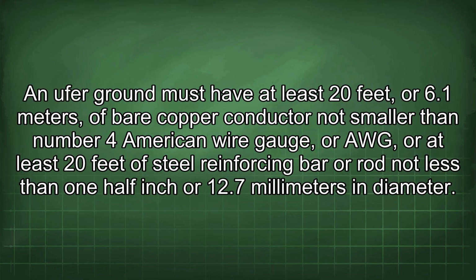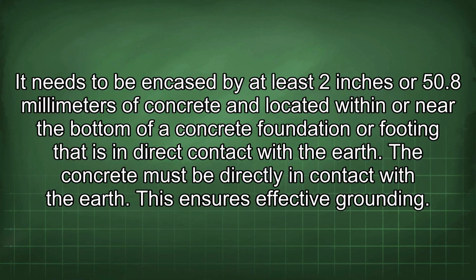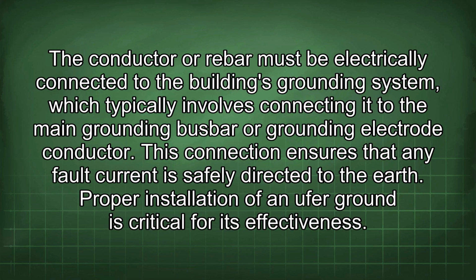A Ufer ground must have at least 20 feet, or 6.1 meters, of bare copper conductor not smaller than number 4 American wire gauge, or AWG, or at least 20 feet of steel reinforcing bar or rod not less than 1/2 inch or 12.7 millimeters in diameter. It needs to be encased by at least 2 inches or 50.8 millimeters of concrete and located within or near the bottom of a concrete foundation or footing that is in direct contact with the earth. The concrete must be directly in contact with the earth. This ensures effective grounding. The conductor or rebar must be electrically connected to the building's grounding system, which typically involves connecting it to the main grounding busbar or grounding electrode conductor. This connection ensures that any fault current is safely directed to the earth.